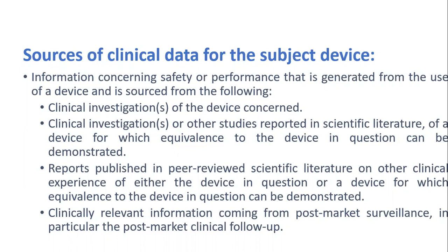Based on those inputs, where the sale of the product is, you're going to collect the adverse event database data from those particular countries to show the clinical evidence of what the risks are and the areas where the device is not working properly, and what control measures the manufacturer has taken to get rid of those risks.